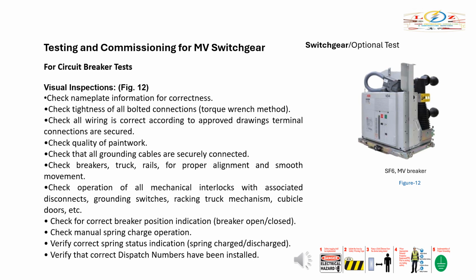Check for correct breaker position indication, breaker open, closed. Check manual spring charge operation. Verify correct spring status indication, spring charge discharged. Verify that correct dispatch numbers have been installed.